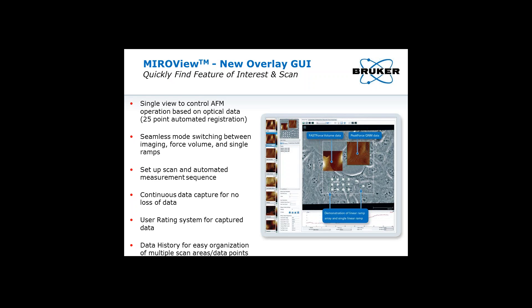An important new capability of the Resolve software is the ability to switch operational modes while the AFM probe is engaged on the sample surface. Previously, users had to withdraw the probe, load a new experiment workspace, adjust parameters, and re-engage. Now, to switch from Peak Force QNM mapping to force volume or force spectroscopy, a user simply clicks the mode icon and draws the area over the optical image. Peak Force QNM, force volume, and single force ramp measurements can all be performed on the same sample within the same workspace. Resolve also enables users to set up multiple measurement sites and program the system to sequentially execute and automatically collect AFM data, combining mode switching so multiple measurement types can be collected on the same location.